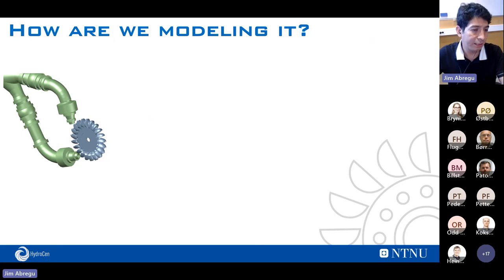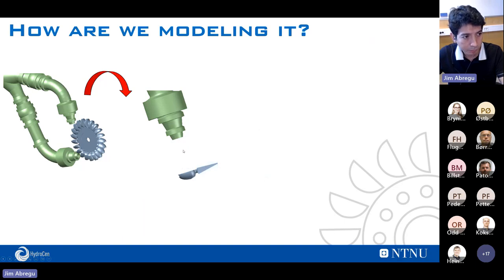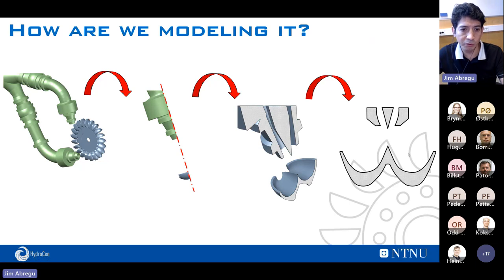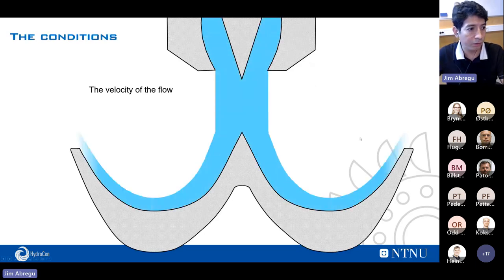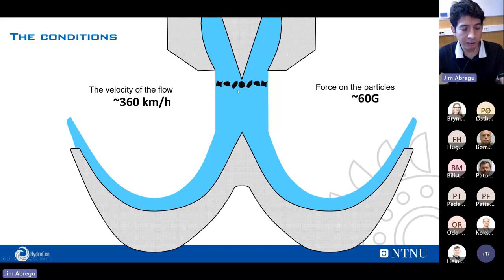And how are we modeling the turbines, and how are we studying them? Usually, we isolate one bucket with the injector and create an imaginary line. With that, we move from three dimensions to two dimensions. So we work in two dimensions to look at how the particles, or the sediments in the water, behave and how they impact the Pelton. In this case, the velocity is close to 360 kilometers per hour, and the force on the particles is close to 60 g.